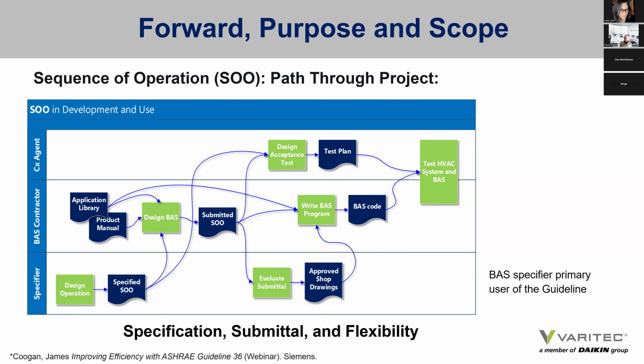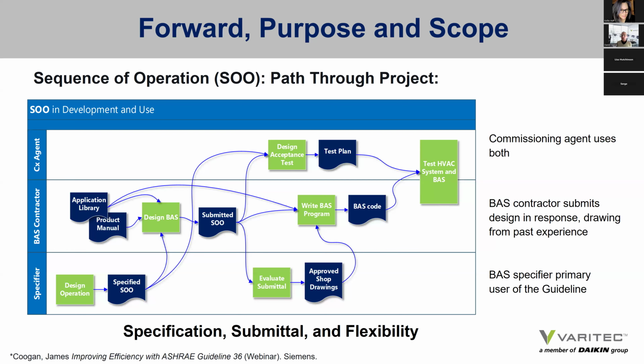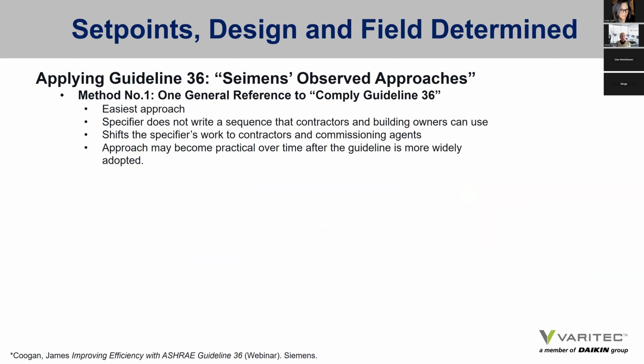So that's the way the actual flow of the process goes. And all of it is to provide a more integrated system approach with everybody speaking a more common form of language. So Siemens shared in one of their videos how they've seen implementation of the guideline in actual documents. There's method 1, which is one general reference to comply with Guideline 36 on drawings. You literally just write that on the drawings. It's the easiest approach for the design engineer.